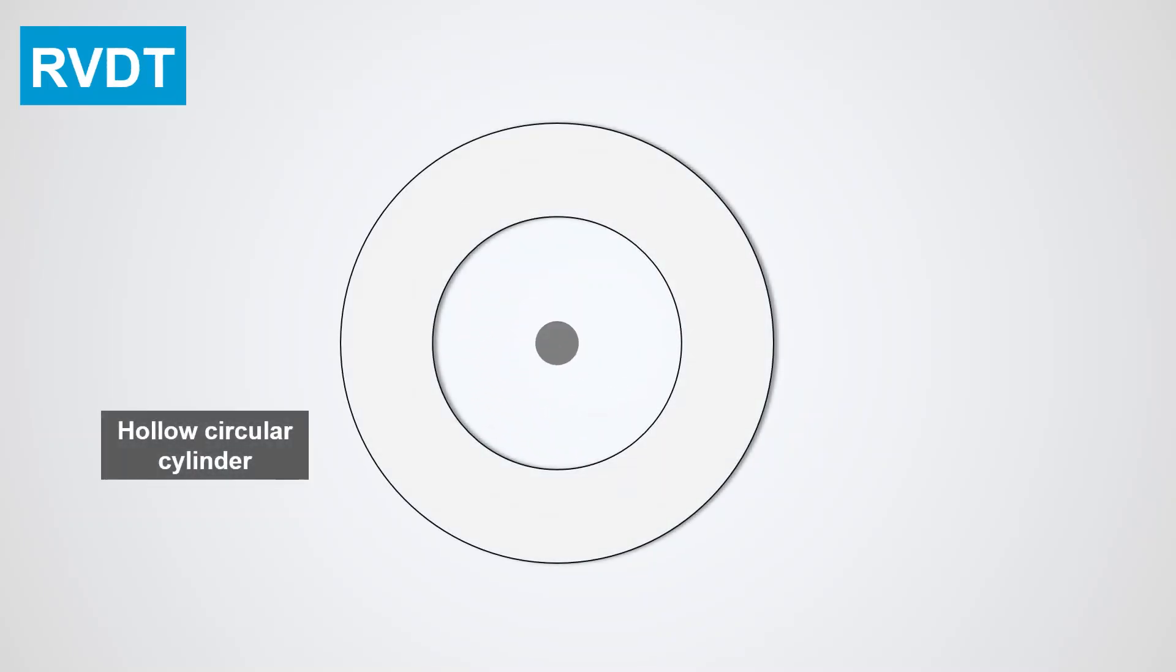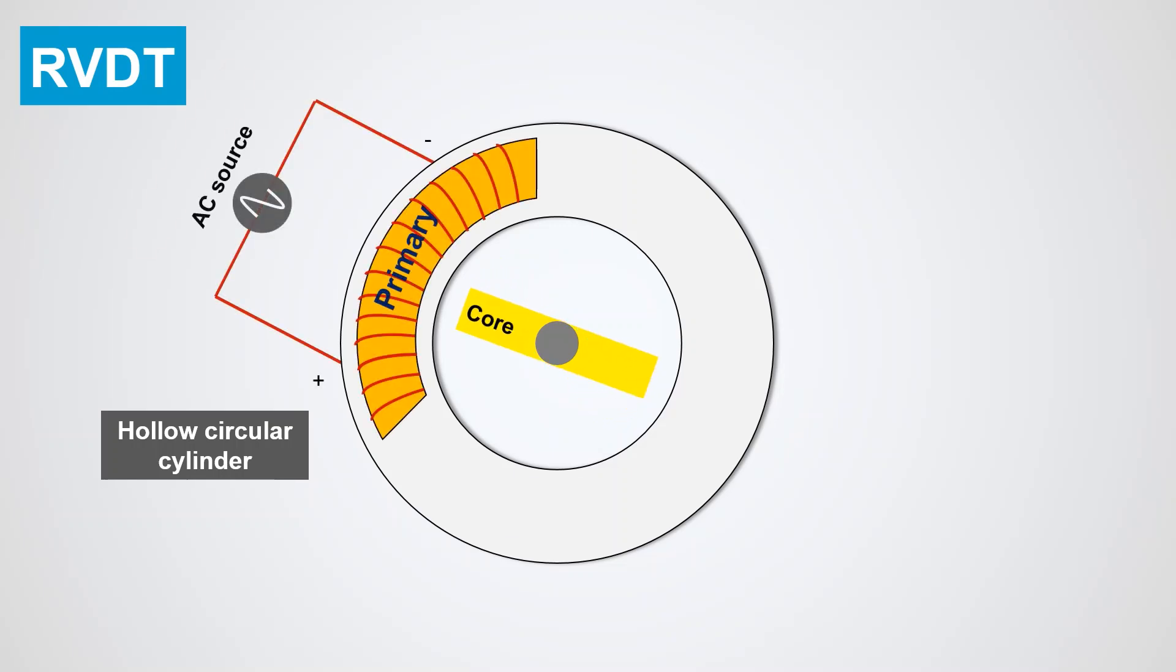An RVDT consists of a hollow cylinder with a ferromagnetically conducted core rotating in clockwise and anticlockwise direction freely between the hollow cylinder. A primary coil is wrapped around the hollow cylinder and is energized by a constant amplitude AC source known as the primary excitation.